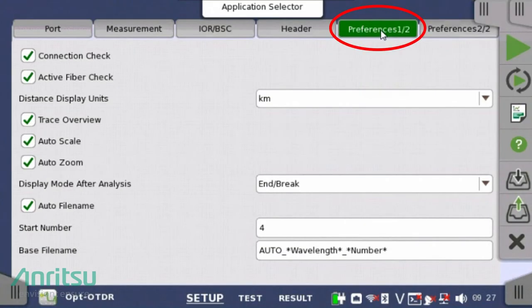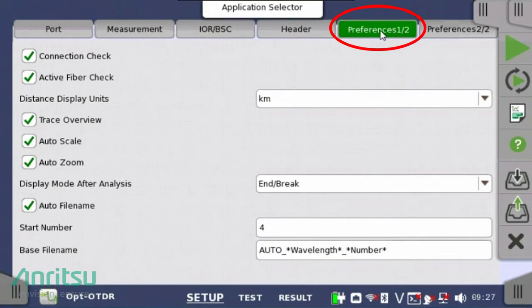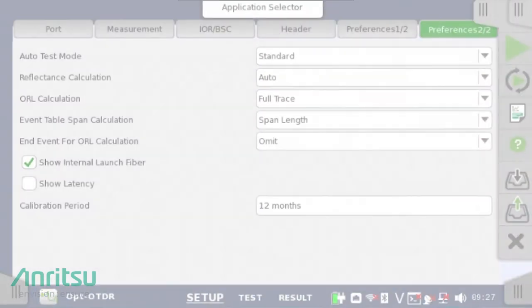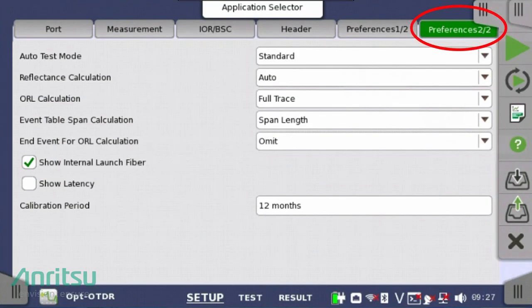In the first preference tab, you can define the distance display units in meters, feet, miles, or kilometers. The connection check and active fiber check verifies fiber connectivity and usage prior to the OTDR measurement and can be disabled if desired. The second preference tab allows the user to define ORL calculation and whether to display the internal launch fiber within the measurement.